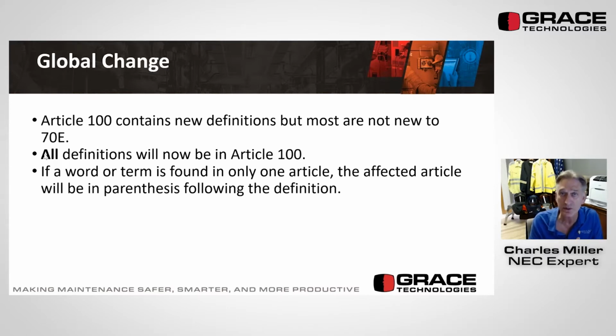In accordance with the 2020 style manual, all definitions have to go to Article 100. Previously, if a word or term was only used in one article, it would be defined in that article's .2 section. For example, in the NEC, swimming pools had many words and terms defined just in Article 680, related only to swimming pools. Now, every term defined in the NEC or 70E will appear in Article 100. If it's used only in one article, that article number will appear in parentheses right after the definition.